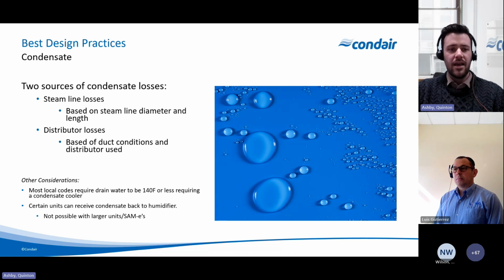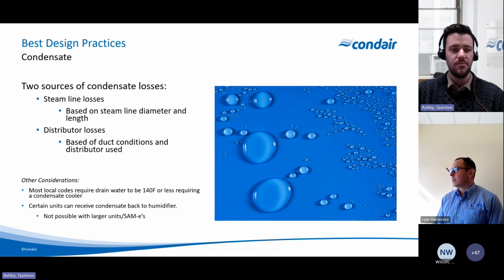Going forward quickly, again, touching on condensate losses. So this is really important. There are two sources of condensate losses. There are steam line losses, which are based on the steam line diameter and the length. So if you have a bigger, longer steam line, you're going to get more condensate. At the same time, there are also losses from the distributor, where we're actually injecting the steam. These are all for in duct as well as in space sometimes. Distributor losses are based on duct conditions and the type of distributor used.